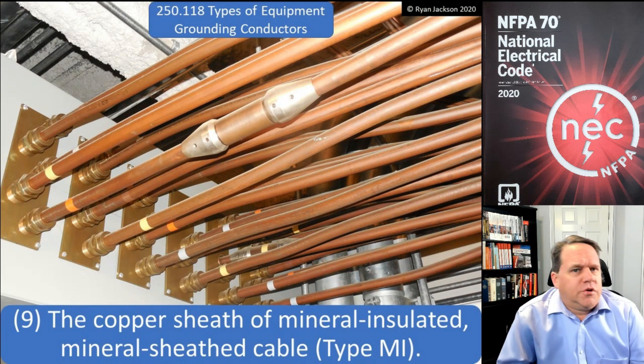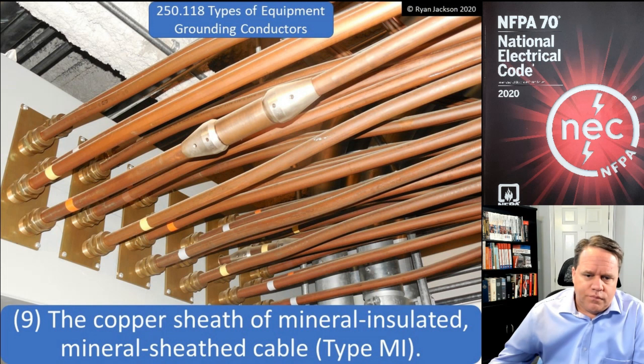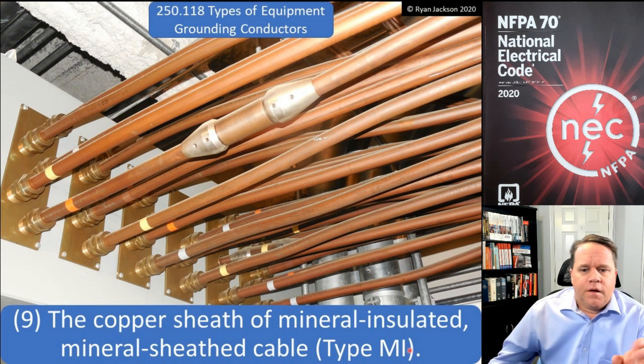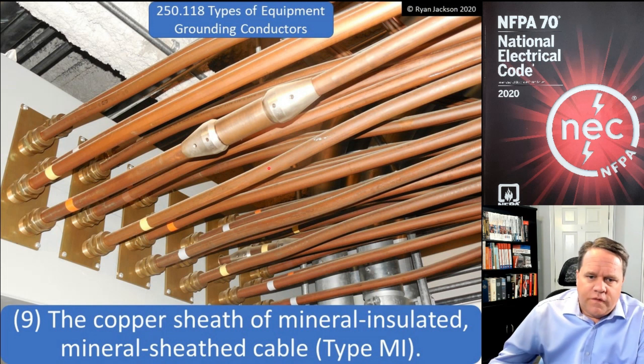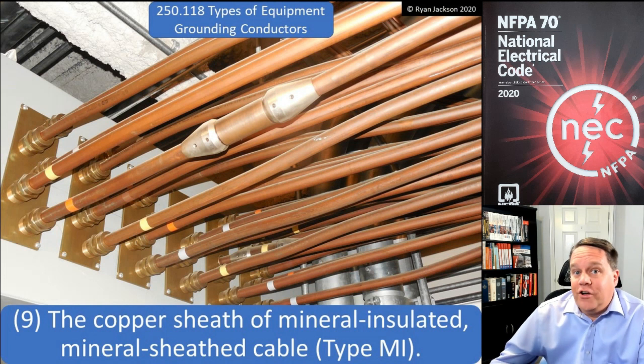You can use the copper sheath of mineral insulated cable. Here we've got some MI cable, and as you can see that copper sheath is going to be a very good equipment grounding conductor.